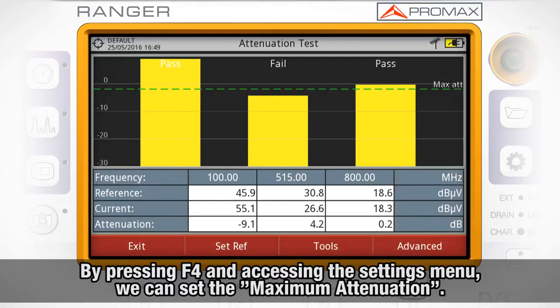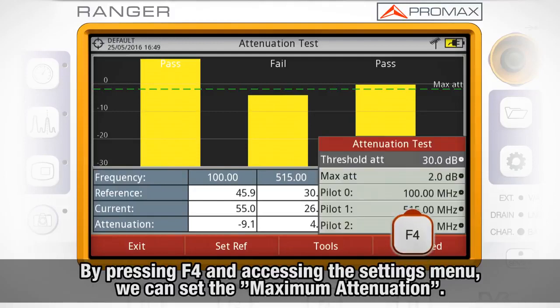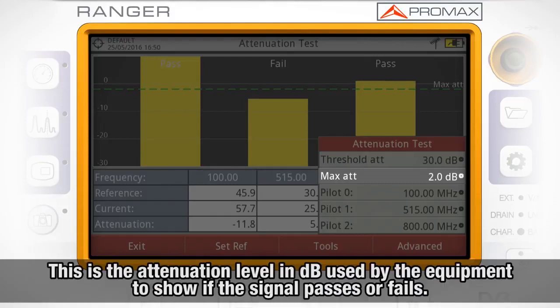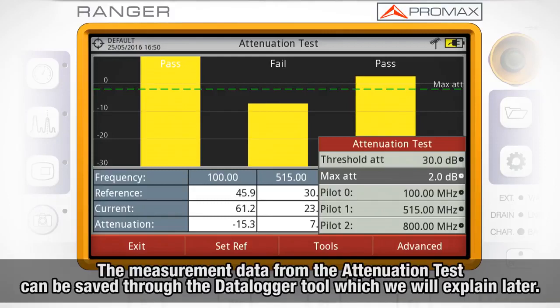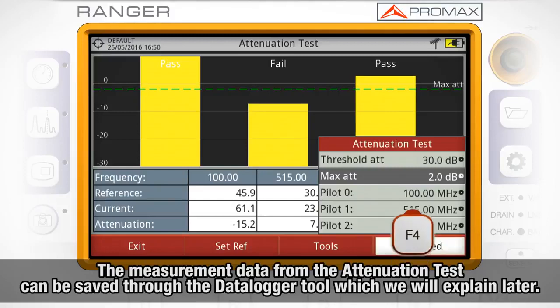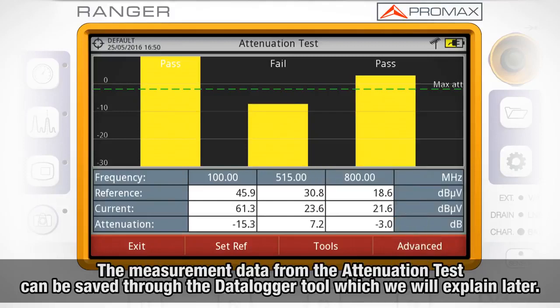By pressing F4 and accessing the settings menu, we can set the maximum attenuation, which is the attenuation level in dBs used by the equipment to show on screen if the signal passes or fails. The measurement data from the attenuation test can be saved through the Datalogger tool, which we will explain later.